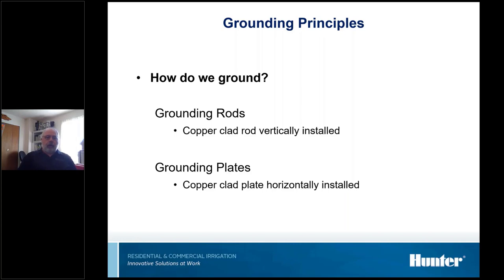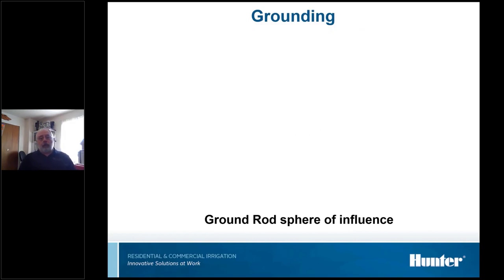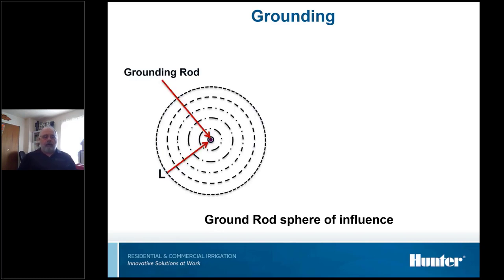There's 96 inch and 36 inch plates. For the most part, we use the 96 inch plates. And these get installed 30 to 36 inches deep. And that's to get them down into where there's more moisture in the soil. So one of the things you've got to understand about grounding is what we call a sphere of influence. This is the area around the grounding device that, when it's doing its job and trying to dissipate the surge into the soil, becomes electrically charged. And so you don't want any electronic devices inside that sphere. If they are, it's likely that the surge will jump right back into what you're actually trying to protect.